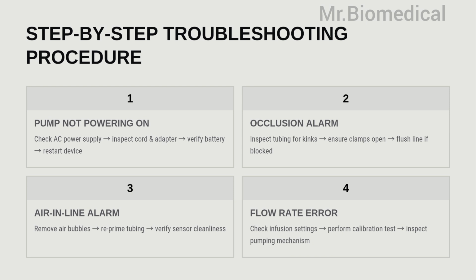Third, air-in-line alarm. Check for air bubbles in the tubing, remove them and reprime the infusion set. Also inspect and clean the air sensor if required. Fourth, flow rate error. Verify the infusion settings entered by the user. Perform a calibration test according to the manufacturer's guidelines. If the problem persists, inspect the pumping mechanism for wear or damage. Always follow a logical sequence during troubleshooting rather than randomly replacing parts.